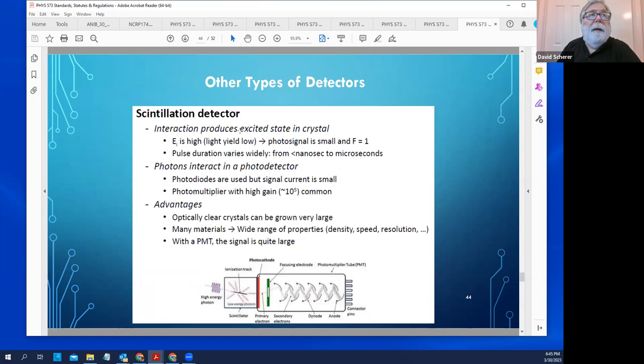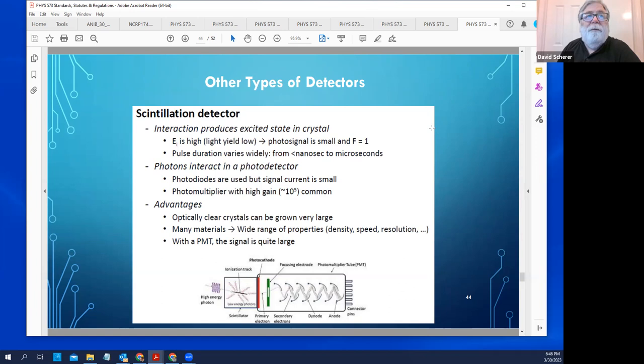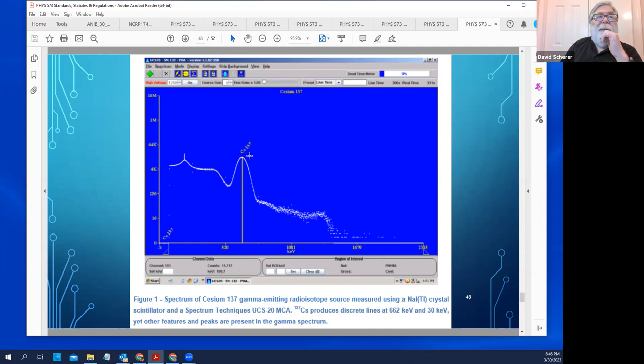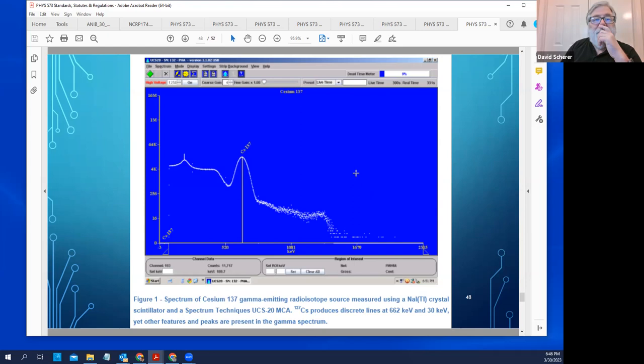Understanding scintillation detectors and photomultiplier tubes is helpful. Also understand how to read a spectrum from a multichannel analyzer (MCA), whether from a scintillation detector or a semiconductor detector. The key features are: the photo peak (from photoelectric absorption), the Compton plateau, and the Compton edge (from Compton scattering inside the detector).